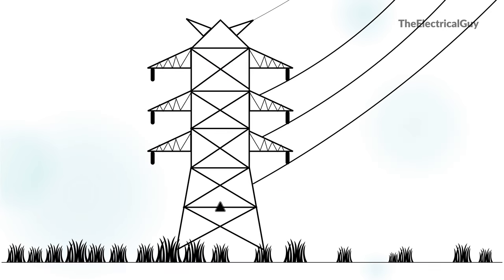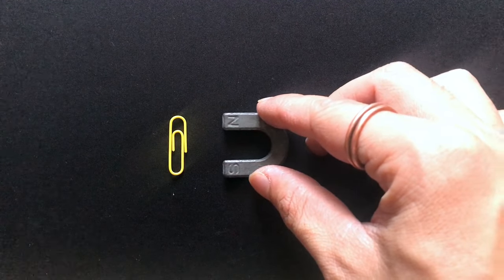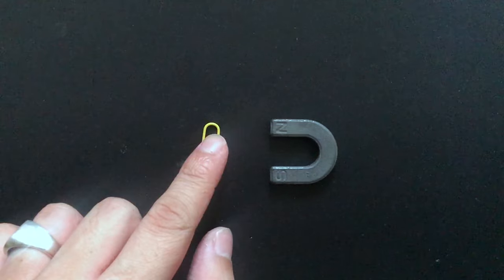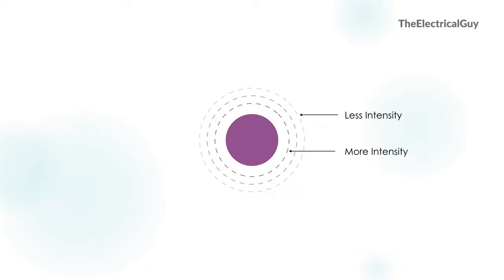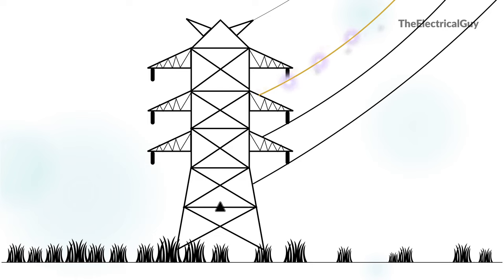The same thing happens with transmission lines carrying high and extra high voltage. The only difference is the distance between the two conductors is more. When the conductor is carrying high or extra high voltage, the air surrounding the conductor becomes ionized due to the electric field around it. Intensity of the electric field is maximum at the surface of the conductor and decreases as we move away — just like a magnet and a metal clip, where force is greatest up close and decreases with distance. As the intensity at the surface is maximum, the air near the surface will become ionized. If the electric intensity is high enough, due to the breakdown of air, a faint violet glow will appear and at the same time a humming noise will be heard. This is nothing but the corona in electrical engineering.